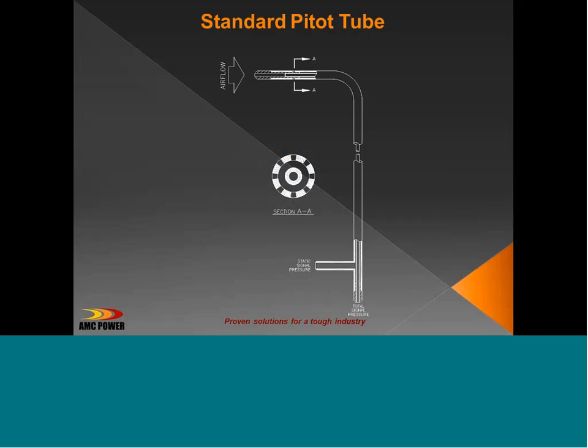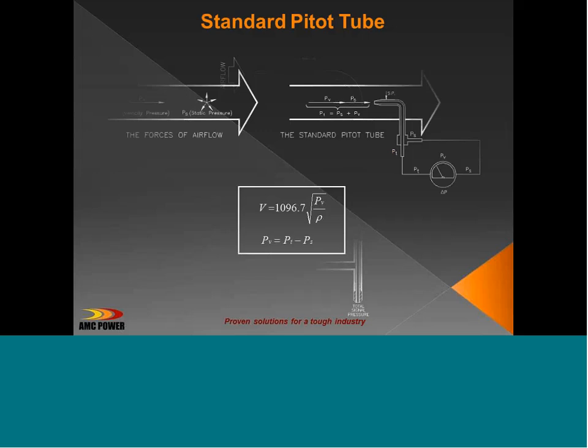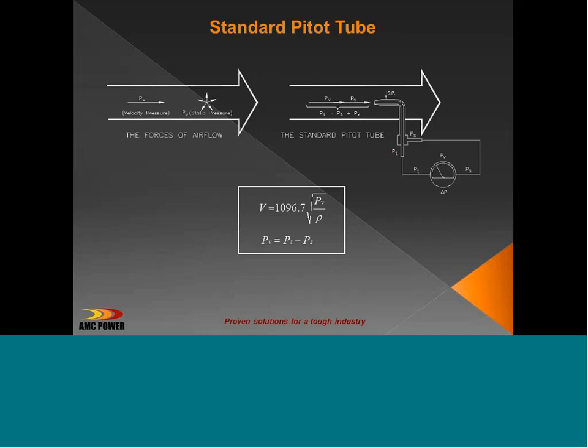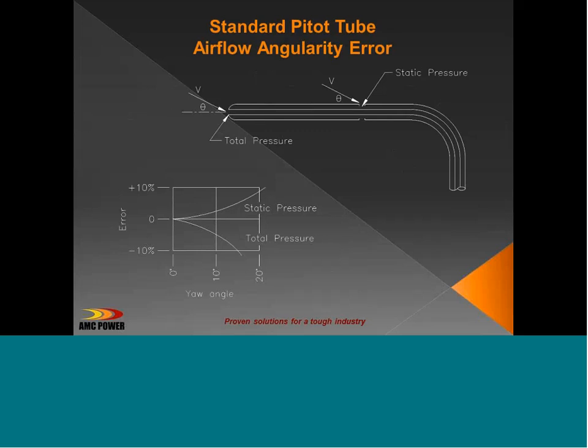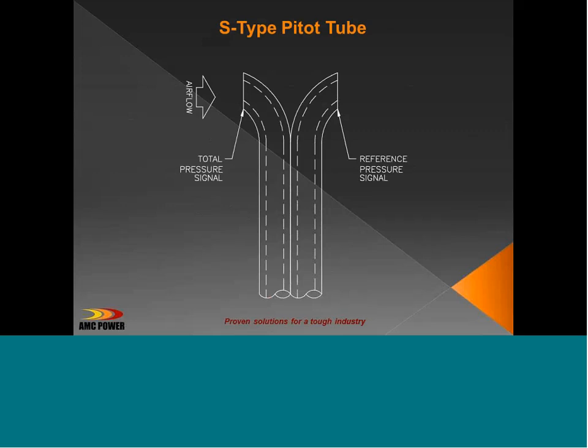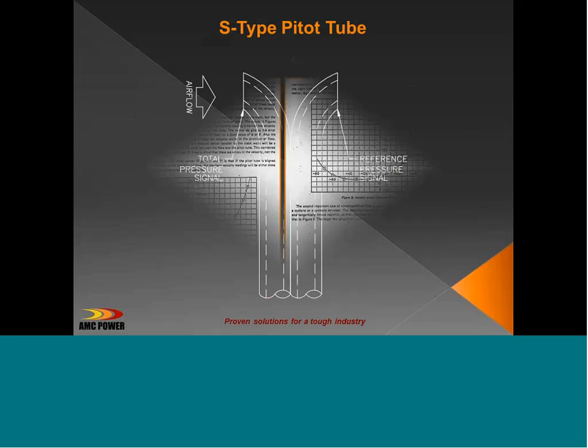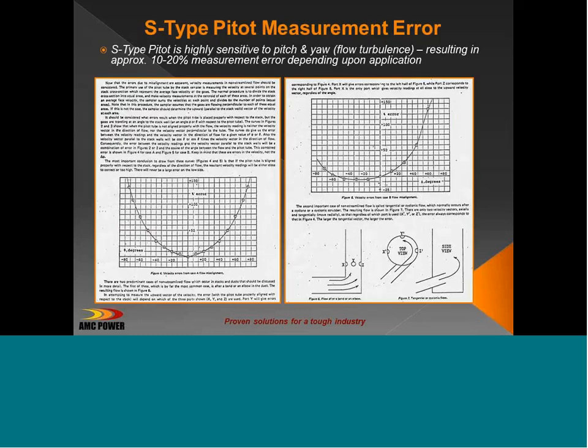Standard pitot tubes aren't used very often in the power industry because they become very erroneous in the event that you have angular flow. And why do you have angular flow? Because you don't have a lot of straight duct or pipe run. So we see that for even a little bit of angular flow, your error on a standard pitot tube becomes dramatic. More common in the power industry is an S-type pitot tube. An S-type pitot tube has a unique feature in that its error is always high. It's always a positive error. So again, as you get into angular flows, you get into very large errors associated with them.